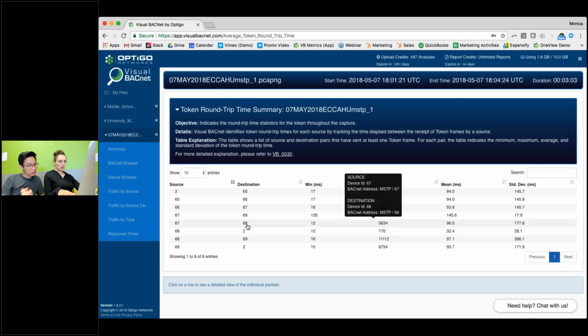So which are likely the source address ones, maybe? Well, the source address was based on IP, so it's not likely under MSTP. You don't think that it's the same ones that are just having problems, going online and offline because of that?